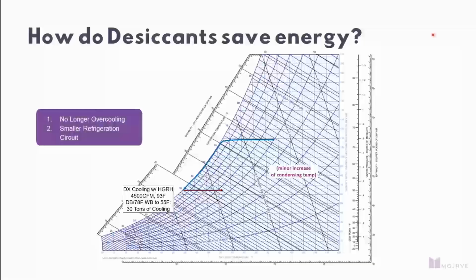So how do desiccants save energy, specifically liquid desiccants? To really understand this, to start, let's look at hot gas reheat style systems. With hot gas reheat style systems, you're going to cool and start brute force dehumidifying as you hit your saturation curve, targeting a final condition. Once you've reached your final condition and dehumidified to your target dew point, you leverage waste heat off the compressor, hot gas reheat, to bring you back up to neutral temperature.